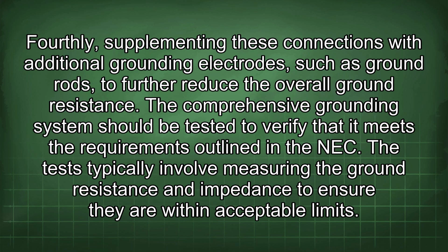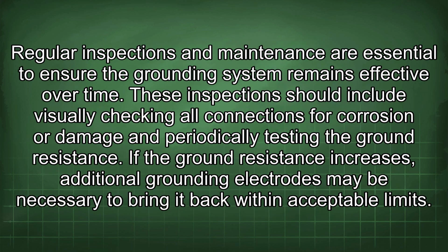The tests typically involve measuring the ground resistance and impedance to ensure they are within acceptable limits. Regular inspections and maintenance are essential to ensure the grounding system remains effective over time. These inspections should include visually checking all connections for corrosion or damage and periodically testing the ground resistance. If the ground resistance increases, additional grounding electrodes may be necessary to bring it back within acceptable limits.